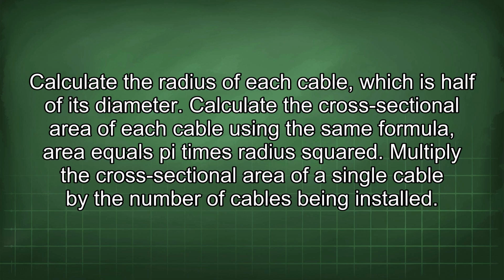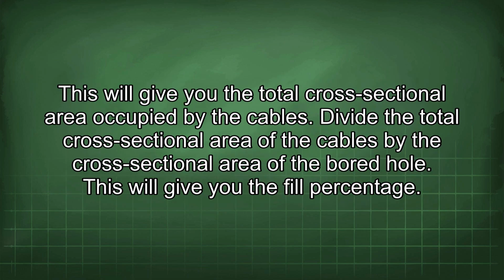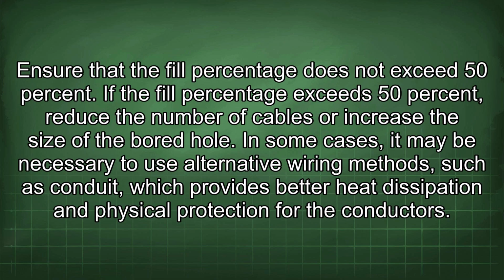Multiply the cross-sectional area of a single cable by the number of cables being installed. This will give you the total cross-sectional area occupied by the cables. Divide the total cross-sectional area of the cables by the cross-sectional area of the bored hole. This will give you the fill percentage. Ensure that the fill percentage does not exceed 50%. If the fill percentage exceeds 50%, reduce the number of cables or increase the size of the bored hole. In some cases, it may be necessary to use alternative wiring methods such as conduit, which provides better heat dissipation and physical protection for the conductors.